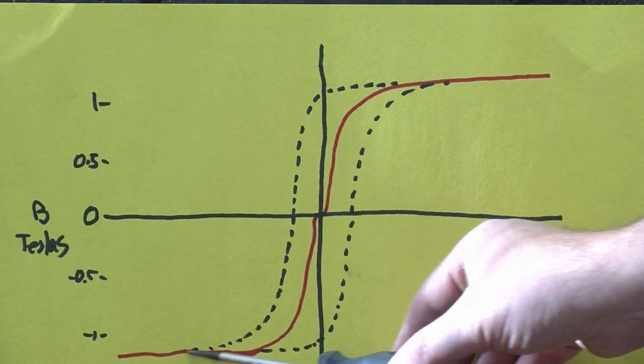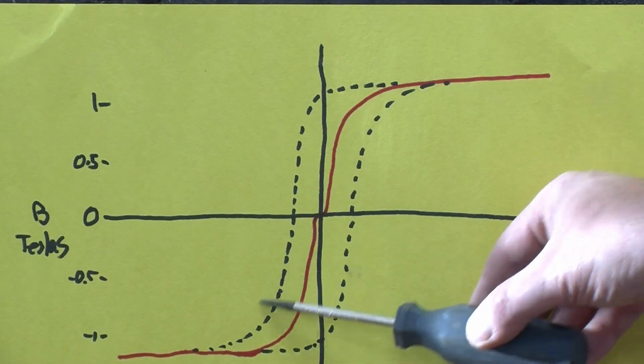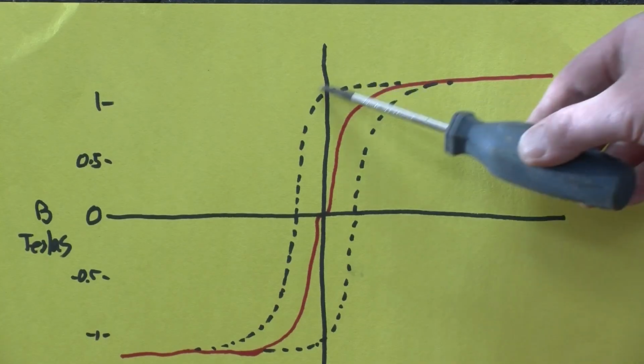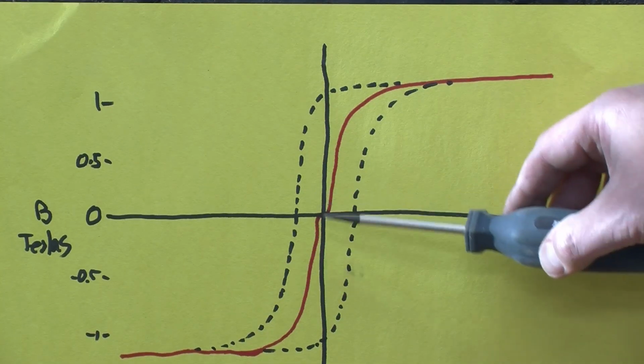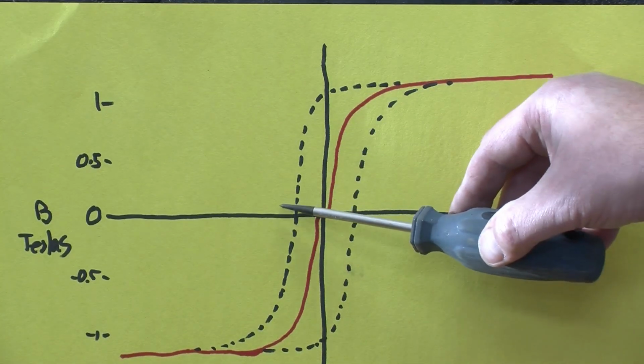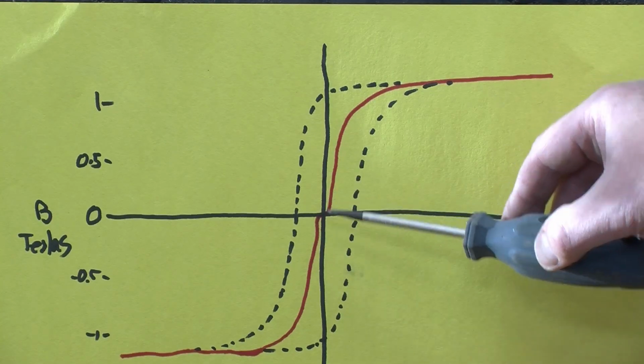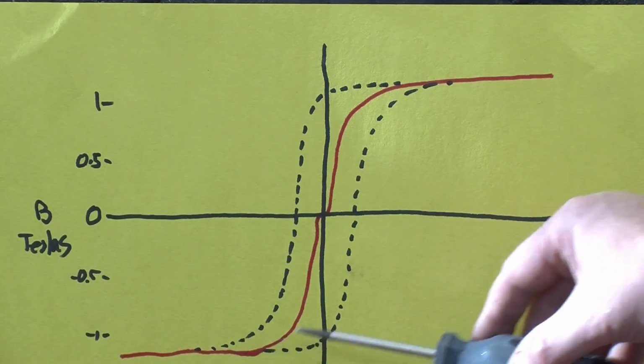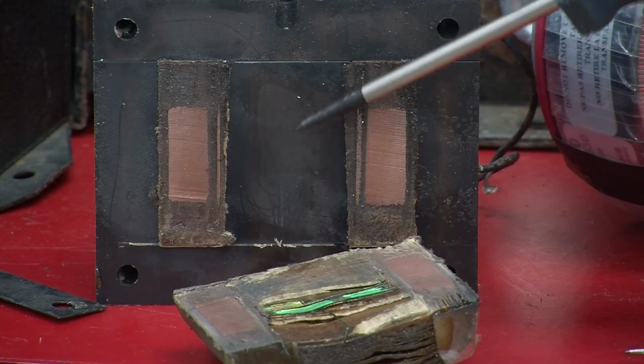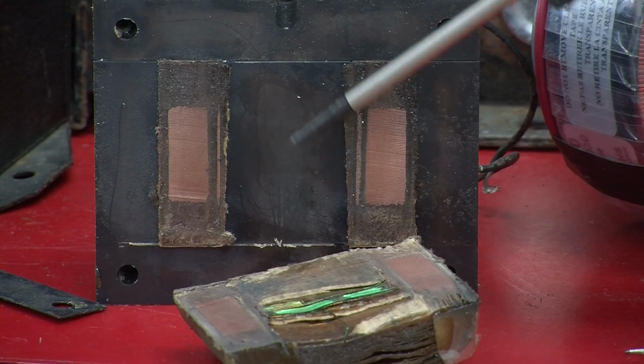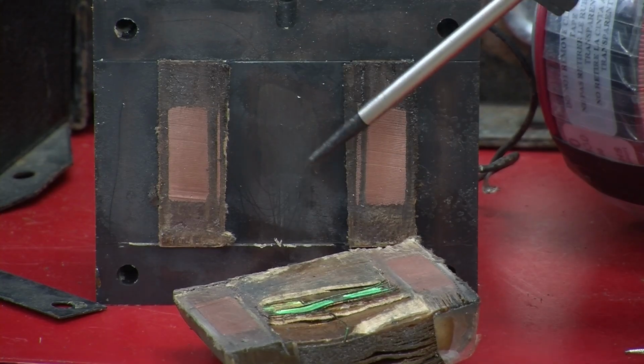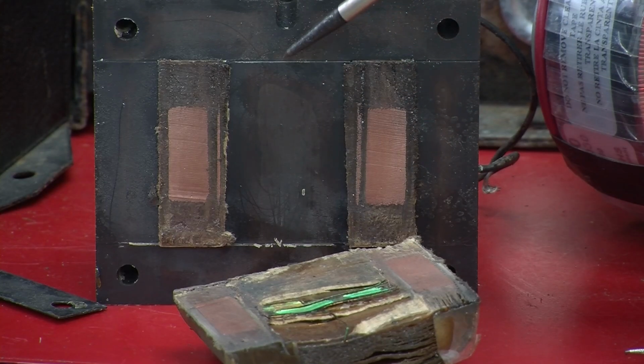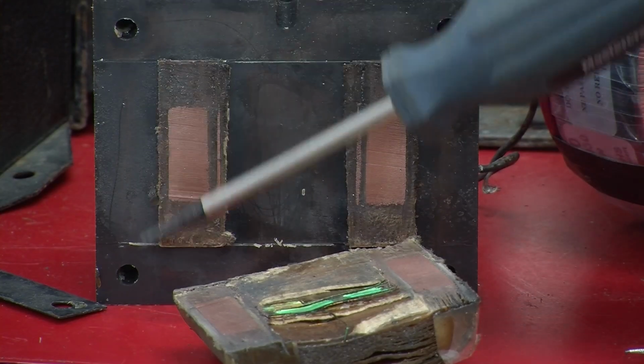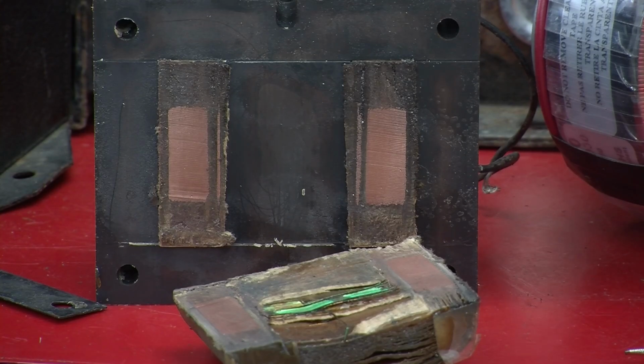It turns out that doing this consumes power in every AC cycle, and that's called the hysteresis losses. And so what manufacturers try and do is use a material that has these two paths as close together as possible so that energy is not lost. So the energy that's lost in the core is called, surprisingly enough, the core losses. Again, essentially the sum of the hysteresis and eddy current losses. And the size of that loss essentially depends on how big the core is, because typically you try and run the core just under the point of saturation.